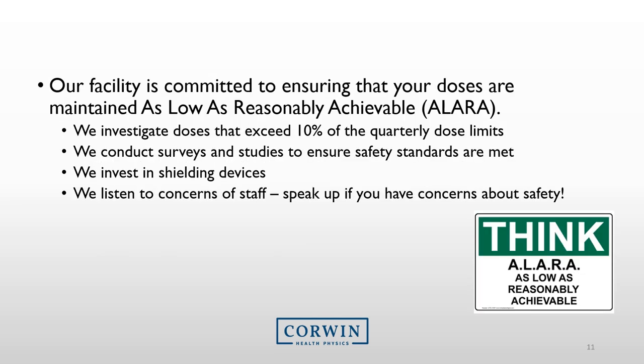Because we assume any dose could potentially increase risk, we still try to maintain radiation doses as low as reasonably achievable — a common regulatory term known as ALARA. We investigate radiation doses each quarter by reviewing dosimeter readings and investigate doses that exceed 10% of the quarterly dose limits. We also conduct surveys and studies to ensure radiation safety standards are met, invest in shielding devices, and listen to staff concerns. Please speak up if you have any safety concerns.